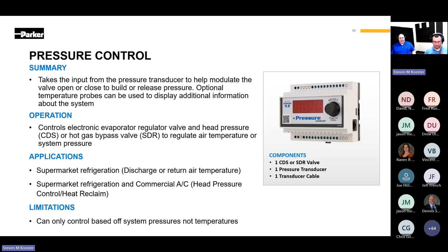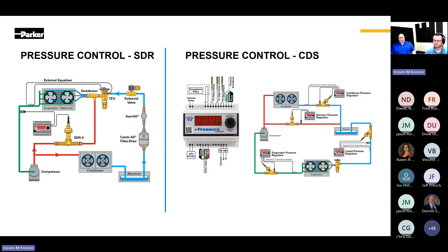The pressure control is used to actuate an electric valve to help regulate the pressures at the point the transducer is attached in the system. This valve can be an SDR or CDS valve depending on multiple applications for refrigeration and commercial HVAC. A pressure control can be used to regulate your condenser, receiver, evaporator, and liquid pressures. Each of these applications has the pressure transducer in the location where you wish to influence pressure. This transducer will read your pressure and transmit it to the controller, which will determine if the CDS valve needs to open or close. The placement of the pressure transducer changes due to the application the controller is being used in.